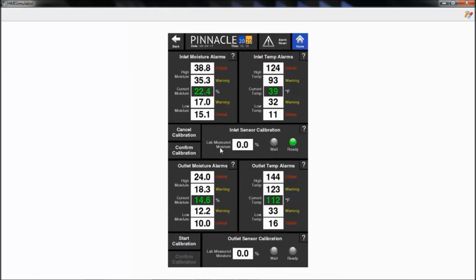If we go to our moisture sensor settings, we see a page that looks like this. This page will be slightly different depending on what sensors you have installed on the machine. If your machine is equipped with both in-feed and discharge sensors, you'll see everything we see here. It looks a little confusing at first, but when you realize that really what we have is 4 blocks like the one we just looked at. We have inlet moisture alarms. All of these are associated together. These 4 white boxes are alarms that are associated with this center value. You can see right now we're not in an alarm condition because 22.4% is between 17.0 and 35.3. We have inlet temperature alarms, outlet moisture alarms, and outlet temperature alarms.